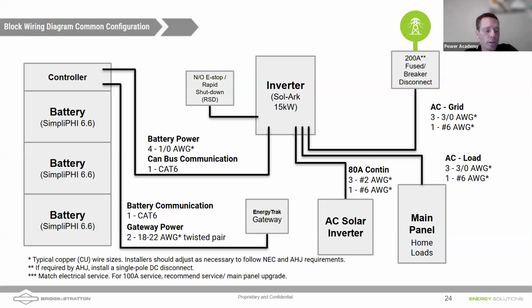Yeah, so SolarEdge inverters have a weird feature to them that they can incorporate batteries to increase self-consumption, but they don't provide any backup power. And I think that that's an unfortunate design flaw with the way SolarEdge has designed their systems, whereas the Sol-Ark being this hybrid inverter, the grid forming is a much better solution, which is why you can find those secondhand SolarEdge inverters so cheap on the market. I've got one of the 7600s in my garage that was $200. So they don't provide backup power.